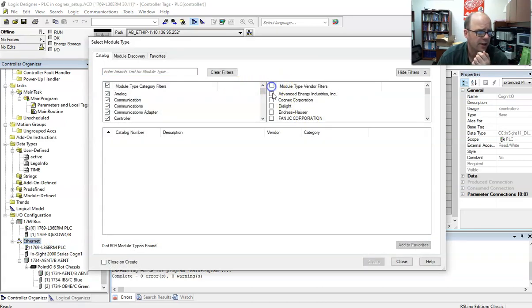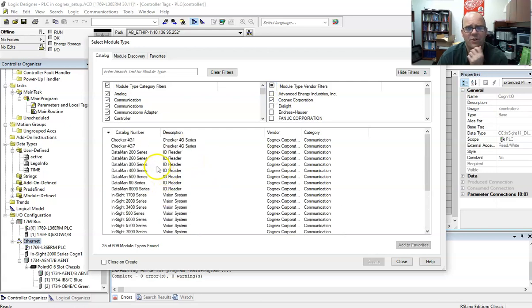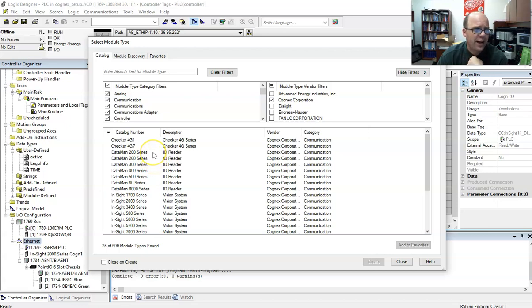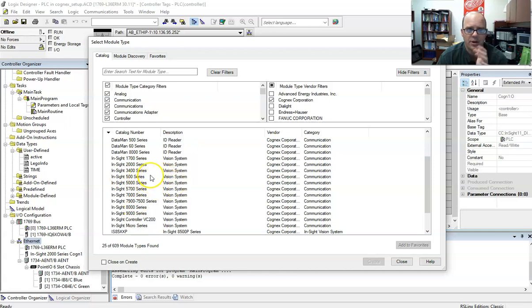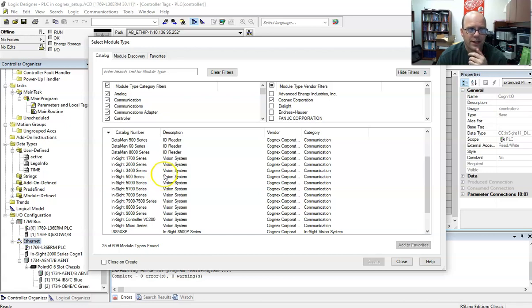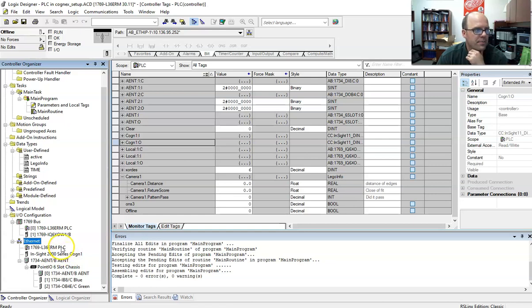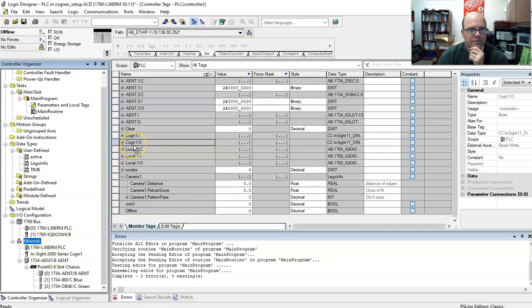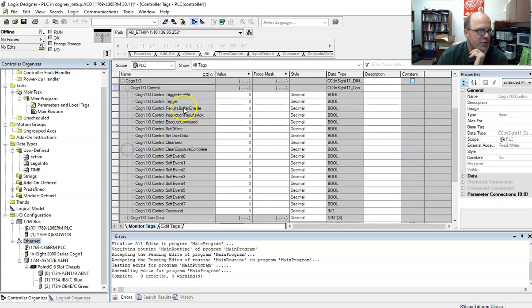If you don't have everything listed here, my recommendation is download the new add-on profile pack. That's what I had to do to install the new add-on profile so that I could get each individual camera installed into my I/O configuration. So I can work with things a little bit easier. I have the In-Sight 2000 series camera. Here I added it in and I just called it Cogn1. As you can see, here's my control bits.